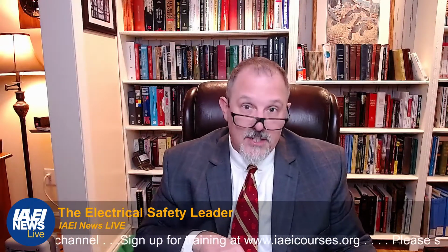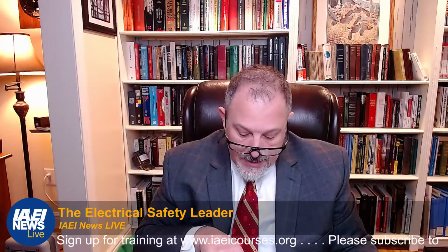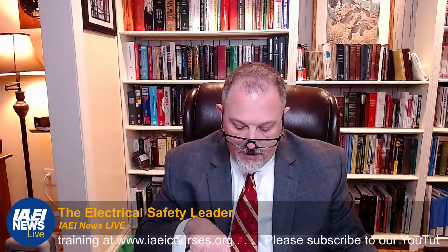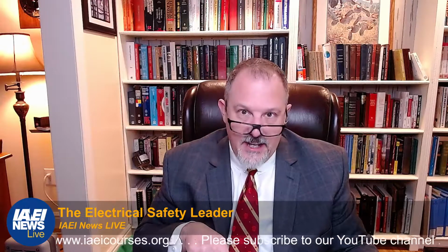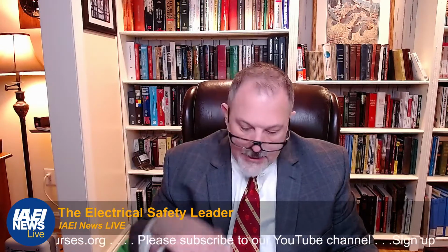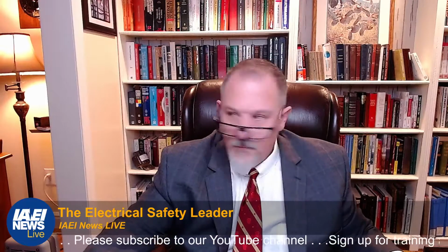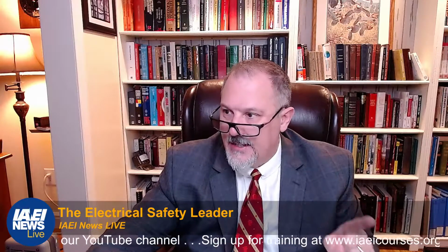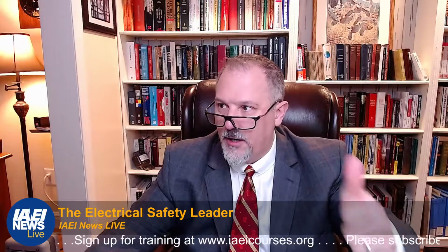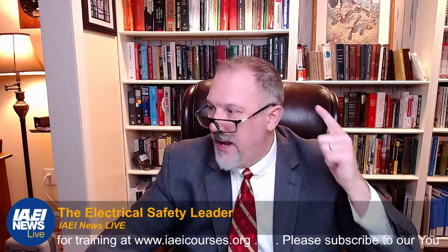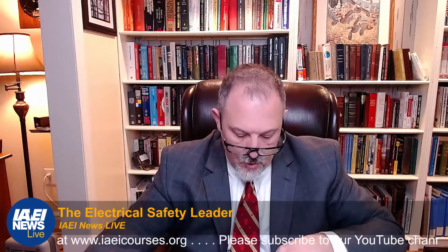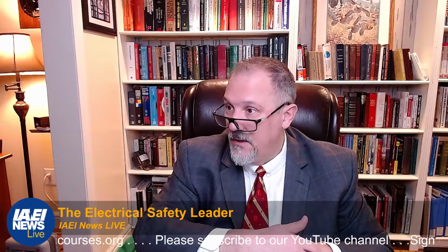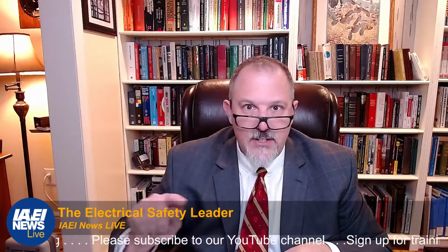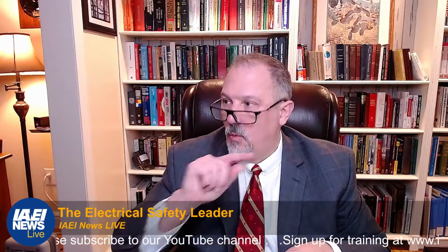Well, it's old 120.5, process for establishing and verifying an electrically safe work condition. And it's all of those steps. So what 110 is telling us now is that, A, your priority is to establish an electrically safe work condition. Unless you do everything in 120.6, or the old 120.5, you shall not consider it an electrically safe work condition.